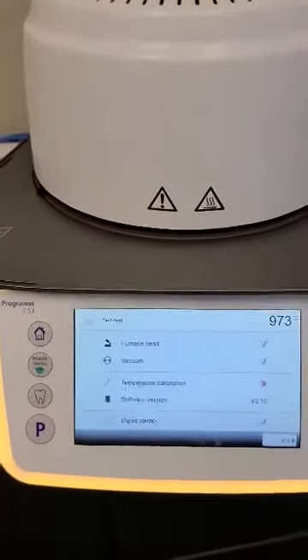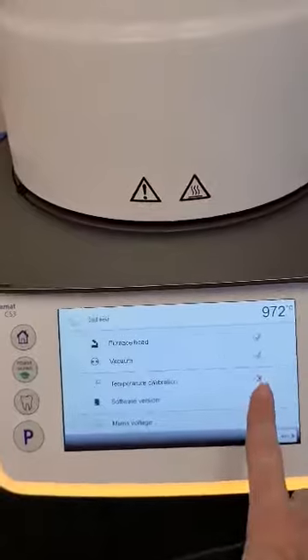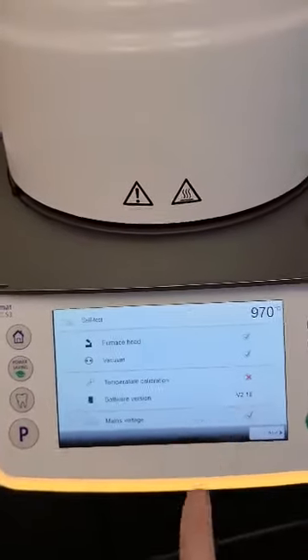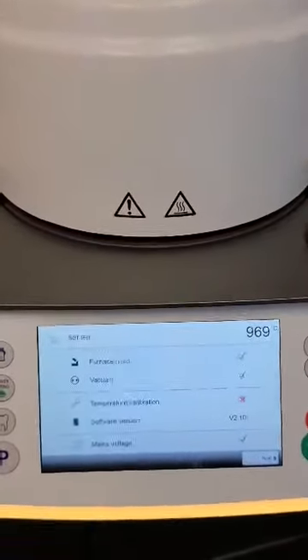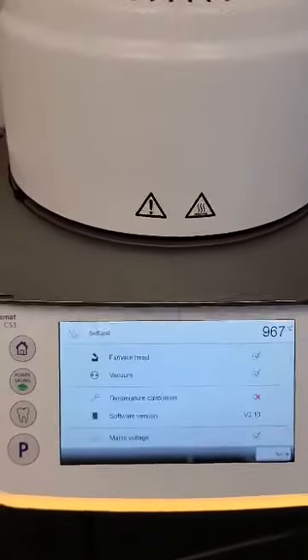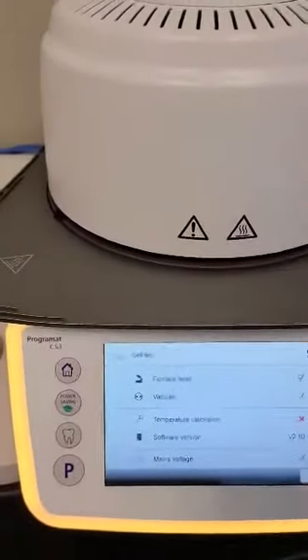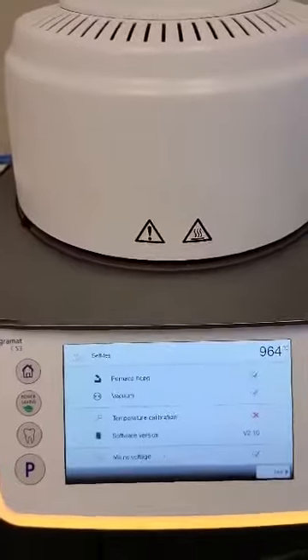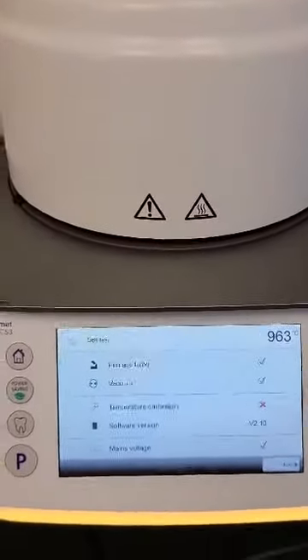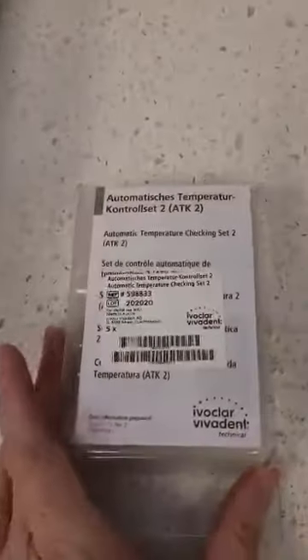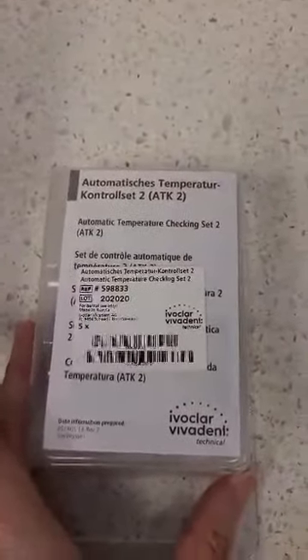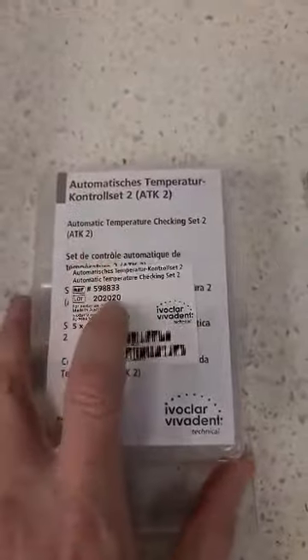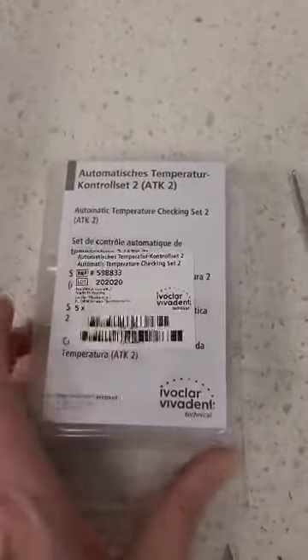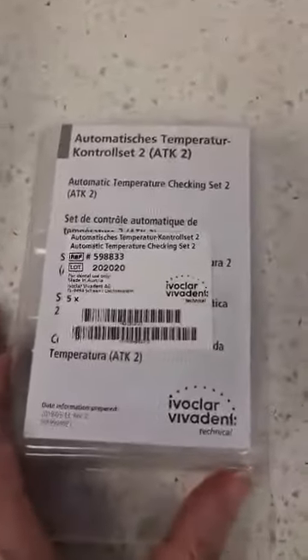So from time to time you've turned on your Ivoclar oven and you have seen this red X at your temperature calibration. That means it's time for its annual temperature check to make sure that the internal temperatures of the oven are performing to manufacturer recommendations. So in order to do that, we need to make sure that you have in stock the temperature calibrators. Now these have a fancy little name, and good luck with that.